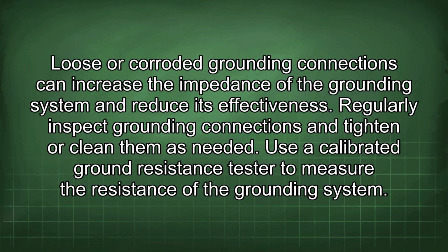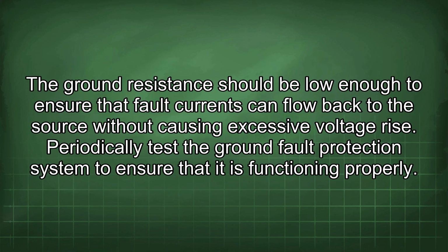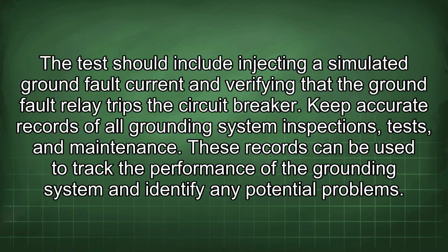Use a calibrated ground resistance tester to measure the resistance of the grounding system. The ground resistance should be low enough to ensure that fault currents can flow back to the source without causing excessive voltage rise. Periodically test the ground fault protection system to ensure that it is functioning properly. The test should include injecting a simulated ground fault current and verifying that the ground fault relay trips the circuit breaker. Keep accurate records of all grounding system inspections, tests, and maintenance. These records can be used to track the performance of the grounding system and identify any potential problems.